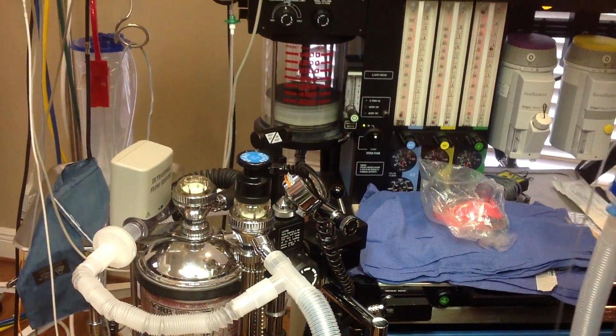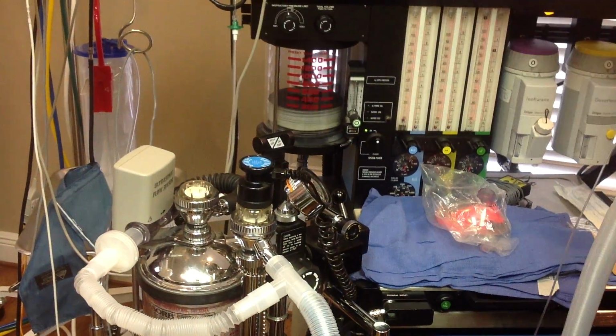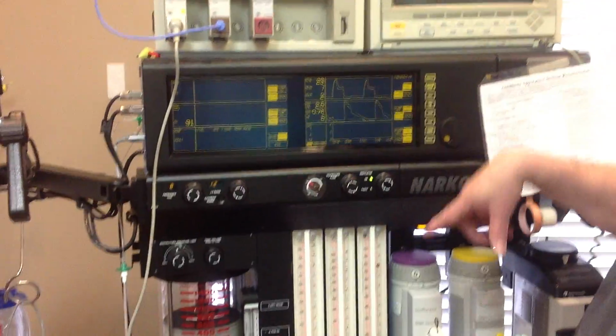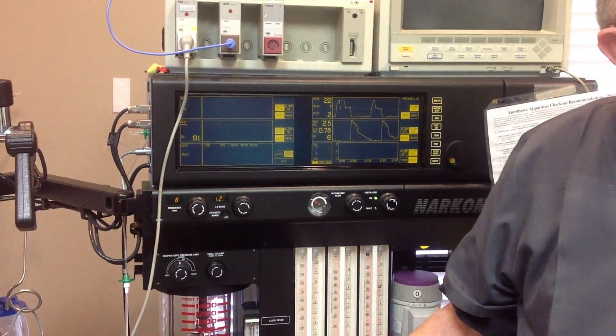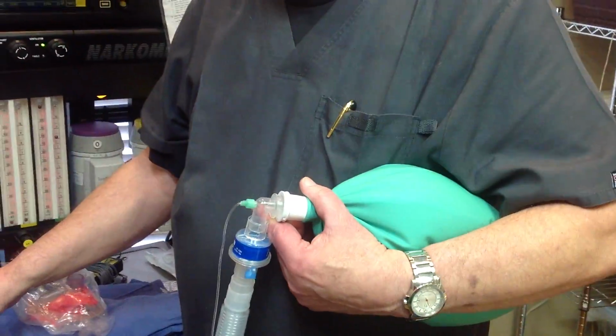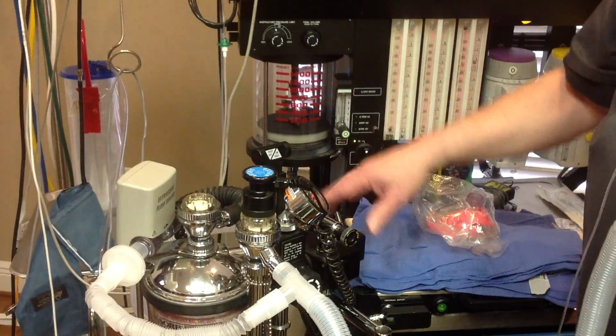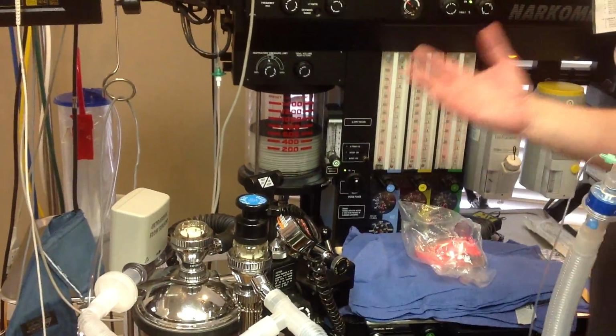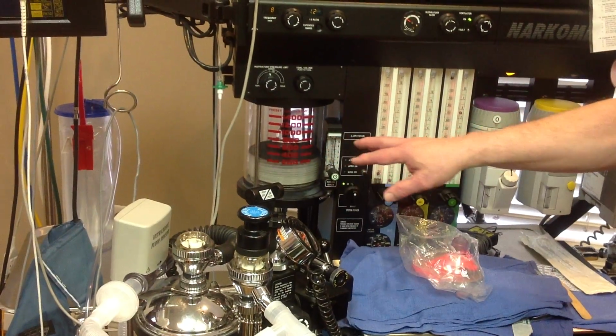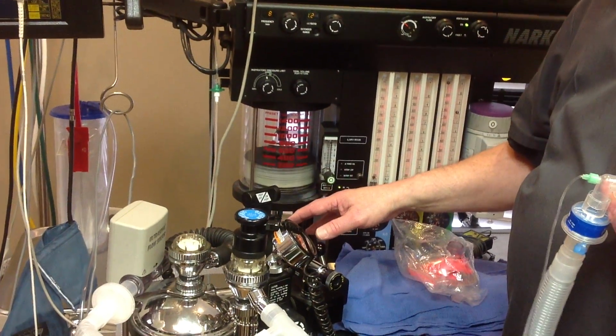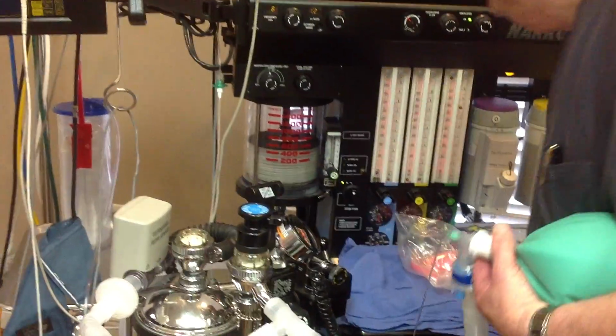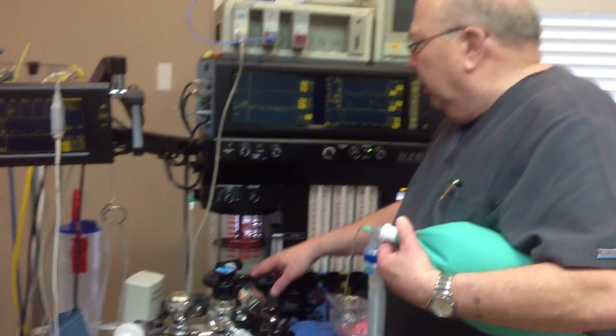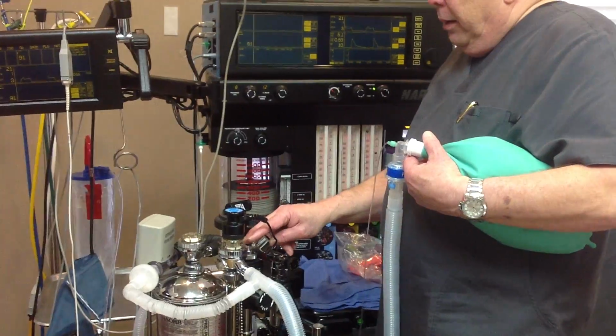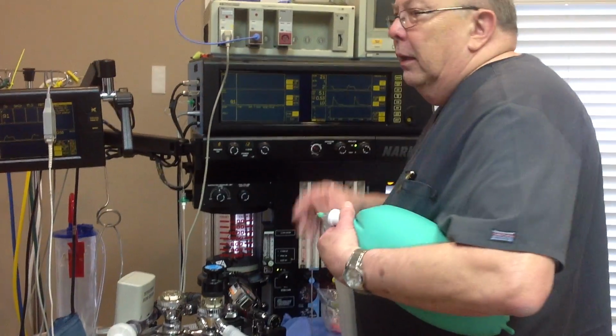Okay. Do I have a tidal volume so that my sensor is working? Yes, I do. And here's my peak inspiratory pressures. See how he's got it under his arm? It's like it's simulating the lungs, right? If you just hold it out, it won't work. You have to have a little pressure to make the ventilator work properly. All right. So it's basically just 3 breaths through the ventilator. That's all you need. You don't have to stand here forever. Okay. Is it going to tell me something? Yeah. So you saw the first breath, inspire, expire. Second breath, inspire, expire, and then check for that in the step.